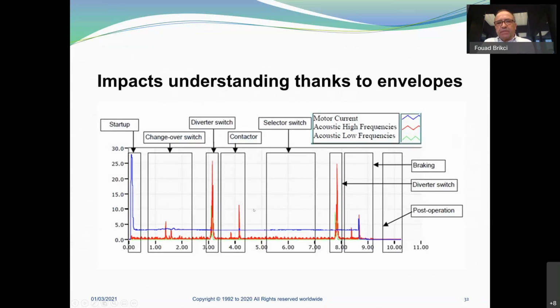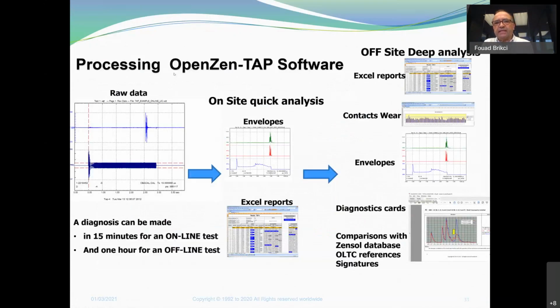We have another part, which is to understand the impacts thanks to the envelopes. Here you can see a typical processing done by our software. Here we have the raw data that gives what we call the envelopes: the low frequency, high frequency, and the current. Here we get an Excel report, and we can do a quick analysis on-site. For off-site deep analysis, we can get Excel reports with the envelopes again, and we have what we call diagnostic cards, and we are able to compare with the Zensol database of OLTC reference signatures.